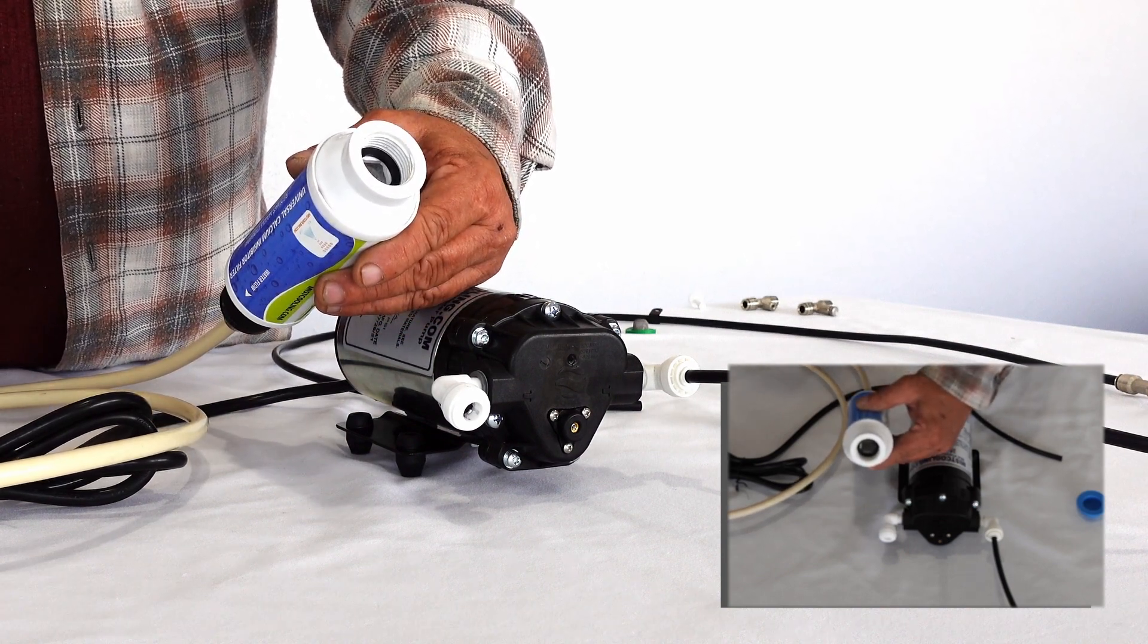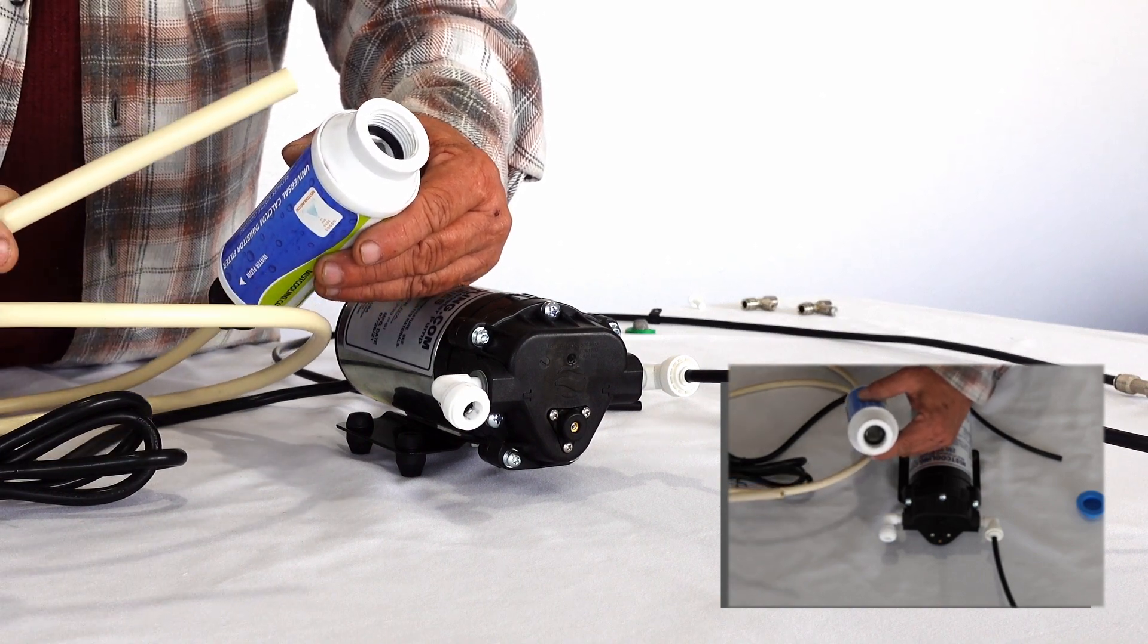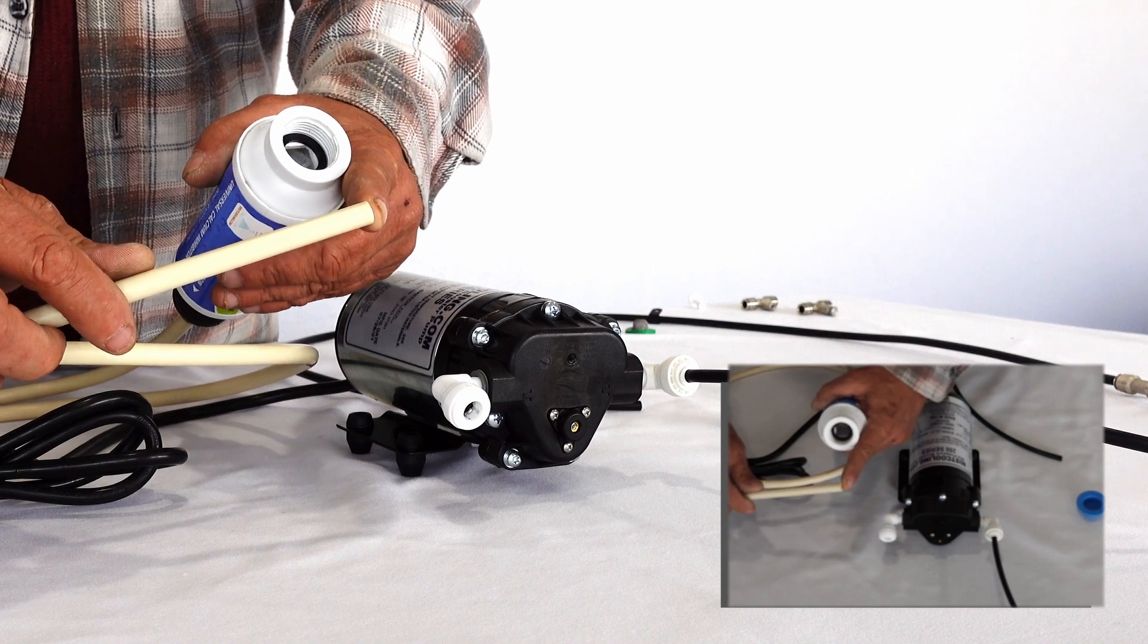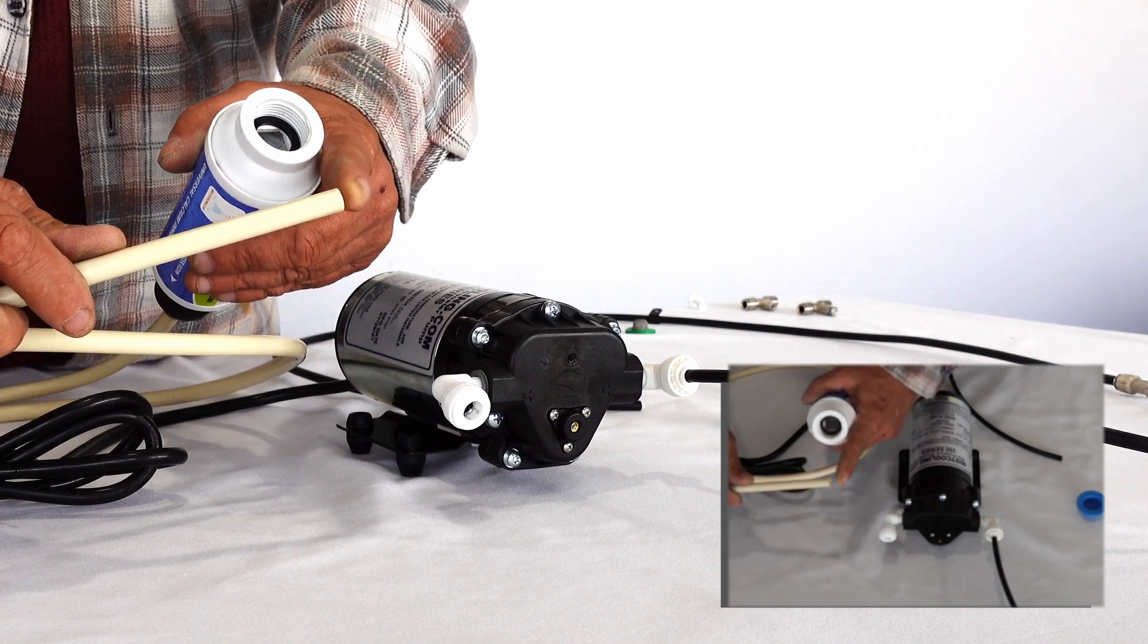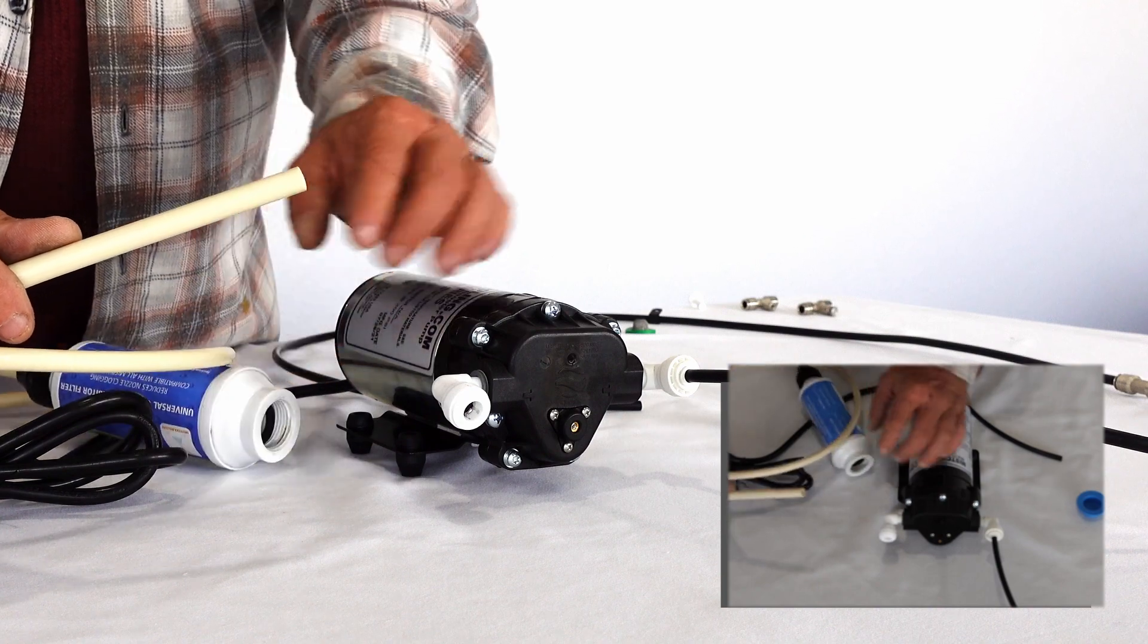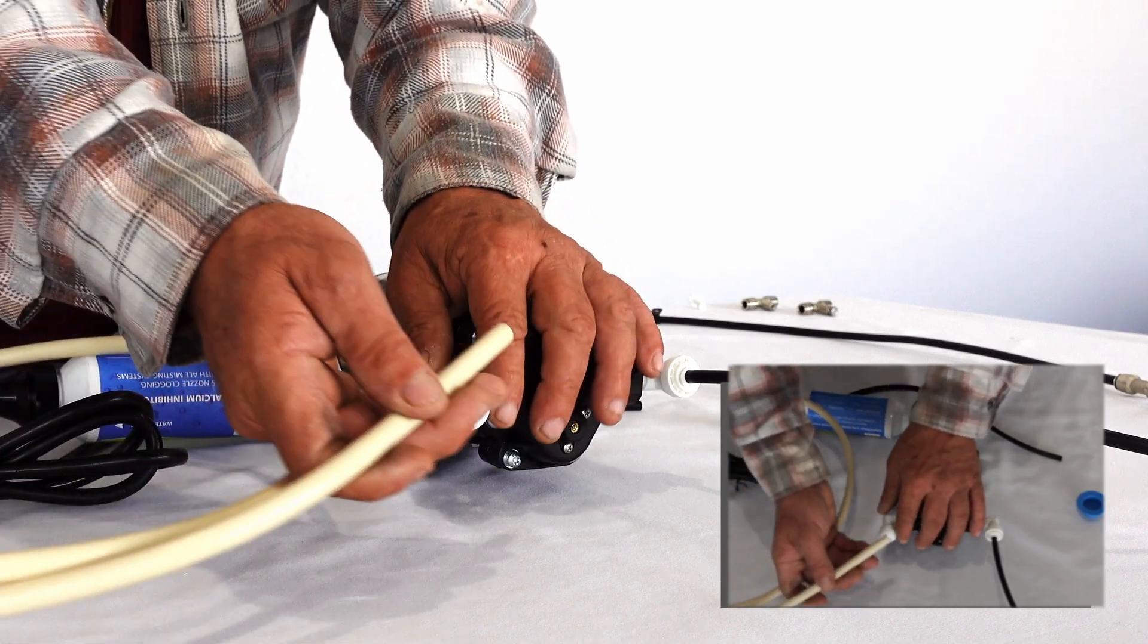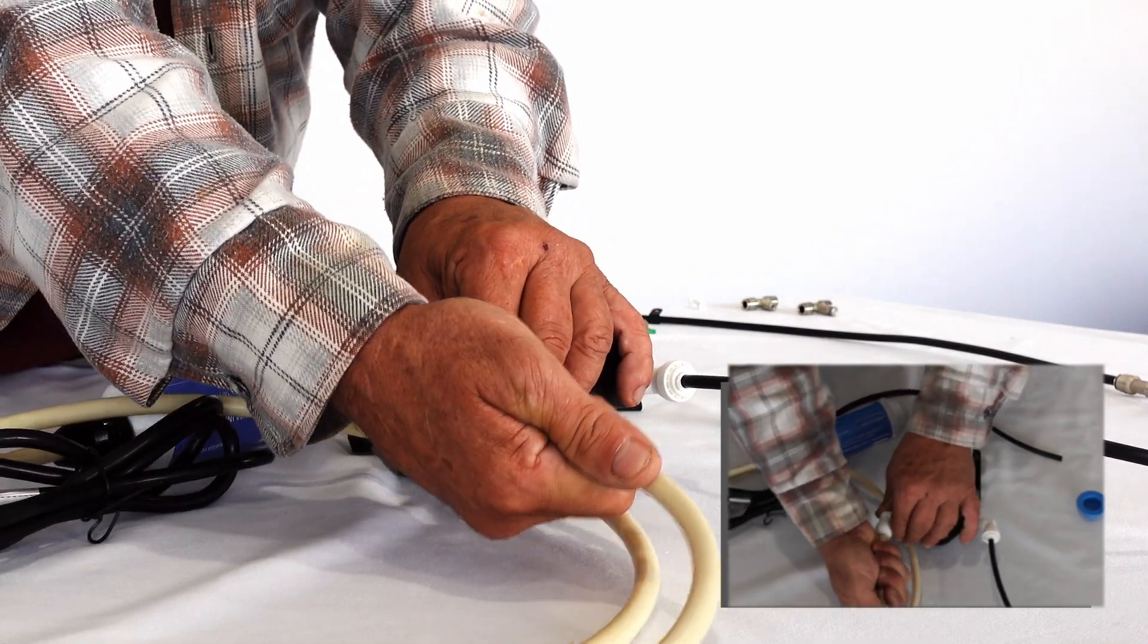Once you screw this onto your water spigot, you will want to turn the water on and flush this line out until you have solid water coming out of here with no air. Once you have solid water you can turn your water off and push this into the inlet fitting.